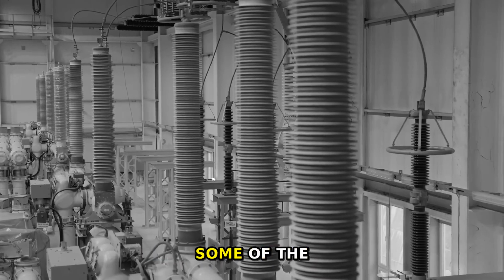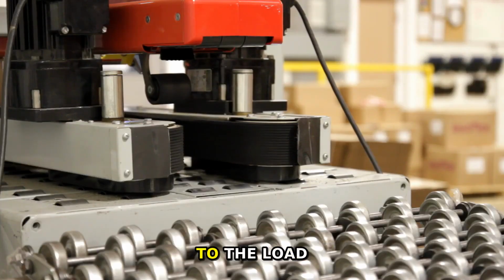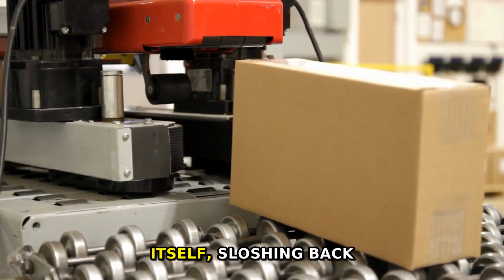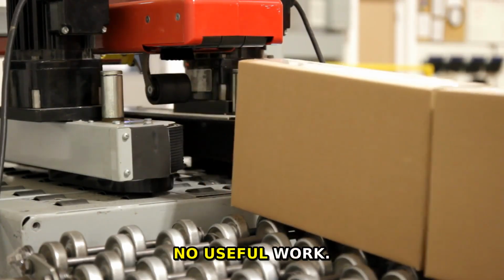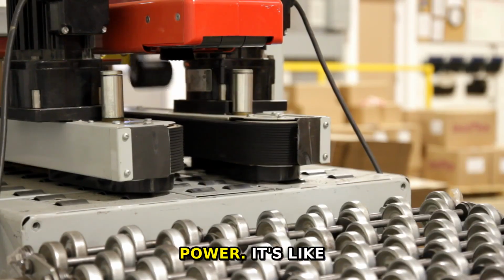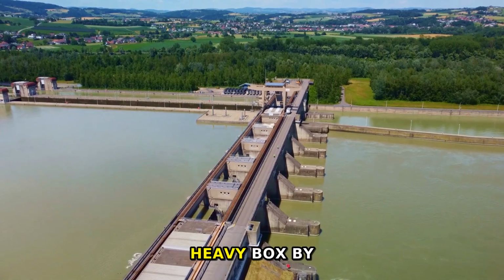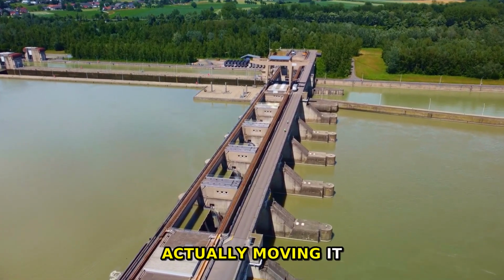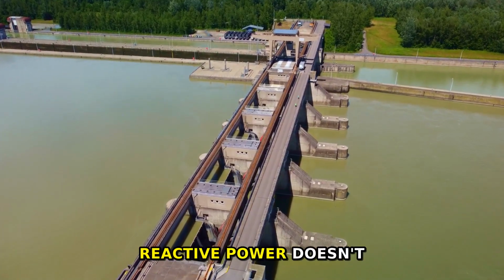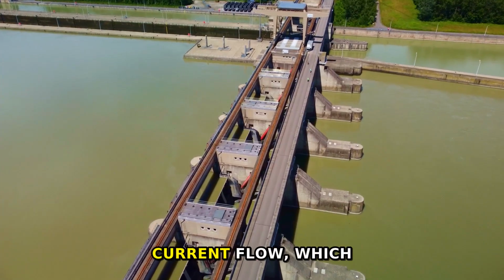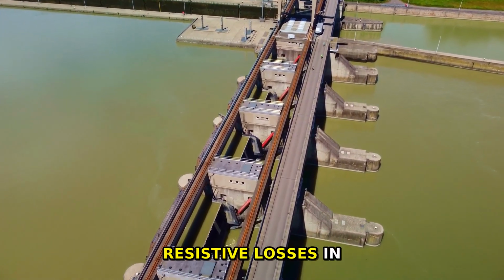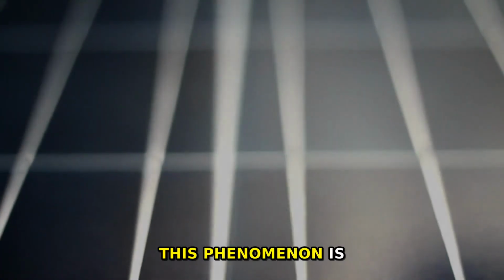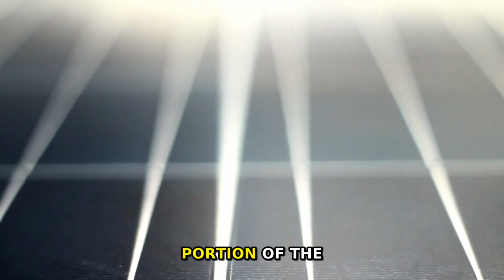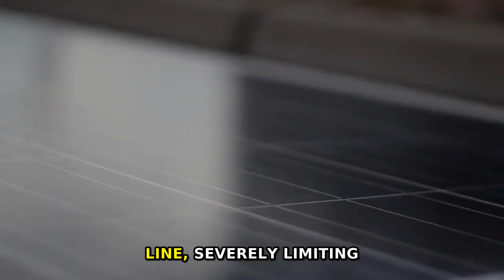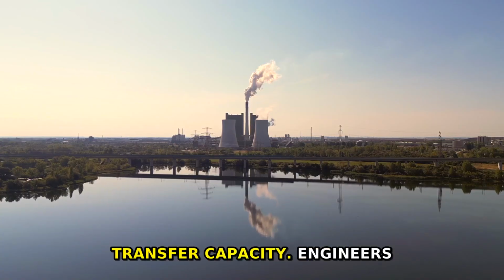This phase difference means that some of the electrical energy is not actually transmitted to the load but is instead stored and released by the line itself, sloshing back and forth, doing no useful work. This is reactive power. It's like a person trying to push a heavy box by rocking it back and forth without actually moving it forward. While this reactive power doesn't consume net energy, it still demands current flow, which in turn causes resistive losses in the line's conductors. This phenomenon is measured in units of volt-ampere reactive, or VAR, and can account for a significant portion of the total current in a long AC line, severely limiting its actual power transfer capacity.